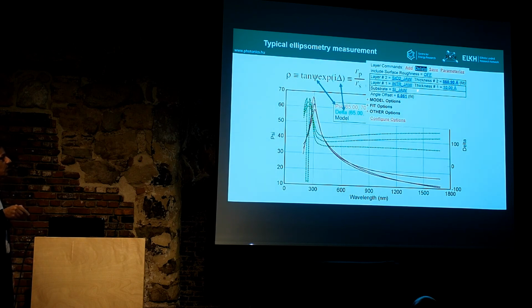This measurement was made on a silicon wafer, single crystal silicon, with an oxide layer of 56 nanometers. You see that we have one model parameter, the thickness—well, two, because the angle of incidence is slightly adjusted, but that's not very necessary. The black lines are the fit to the measured data, shown as colored lines. So with one parameter, we have a very good description over a very broad wavelength range.